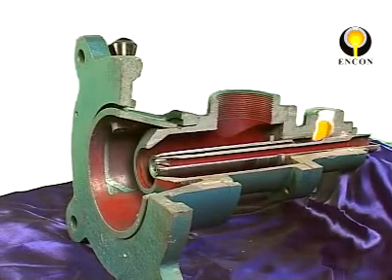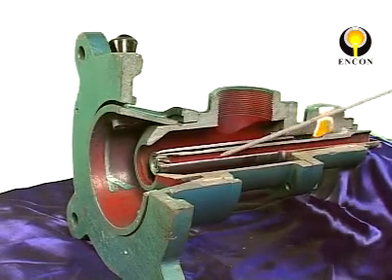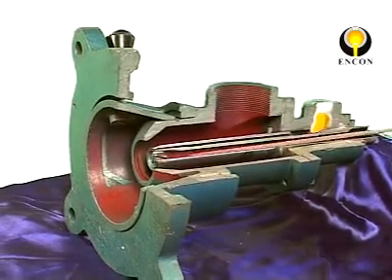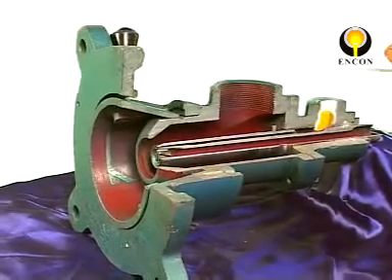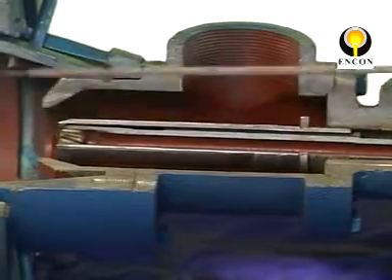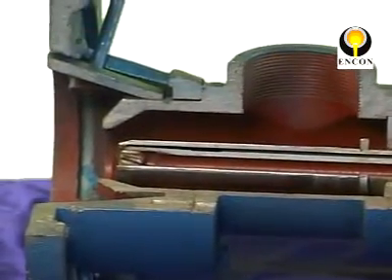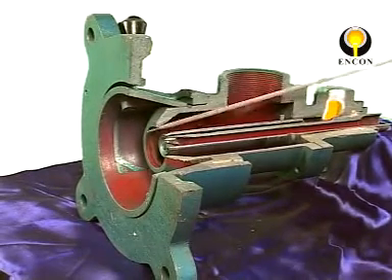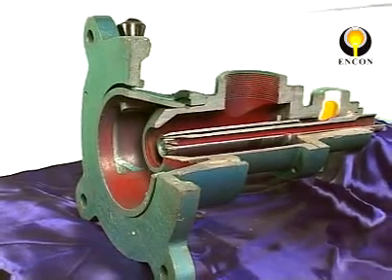Now, when the oil comes through this little film, if you can see, the air coming from inside has a swirler and twirls the oil outwards. The oil coming outside from there obviously goes in flow like this in a cyclone and on the top, another layer of air cuts through oil, so the oil is entrapped between two layers of air.